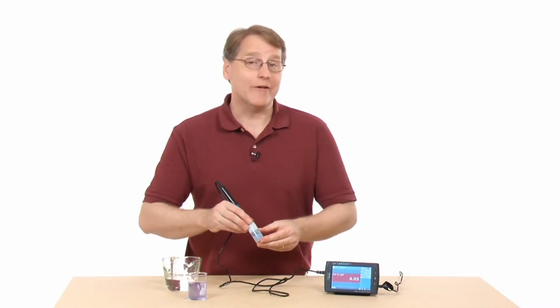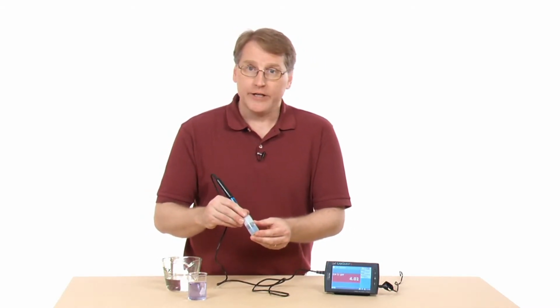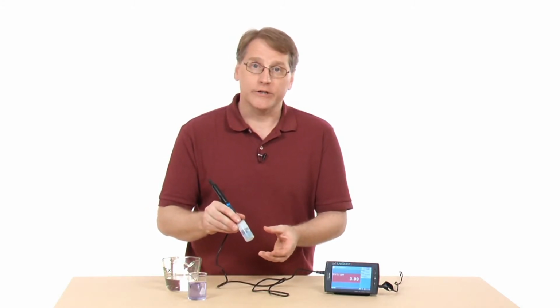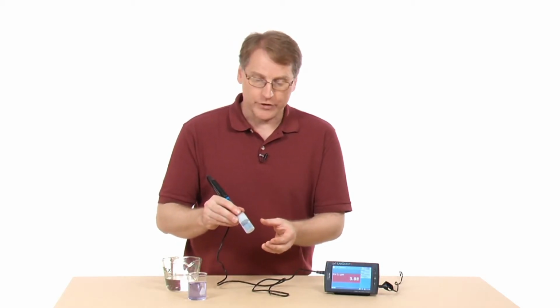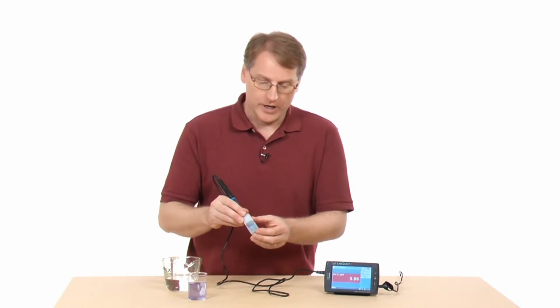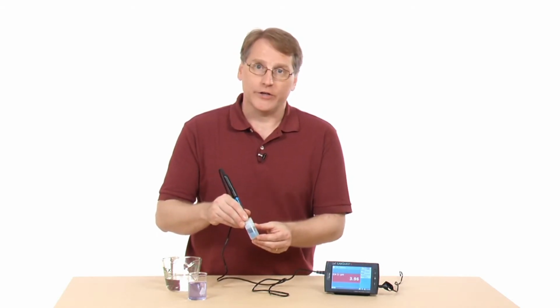People ask about, do I have to calibrate the sensor? And the answer we'd like to say is no. In general, you don't. You're often interested in the change in the pH value, or you want a measurement that you're not worried about out to the hundredths place or something like that. So you can use the stored calibration on there.